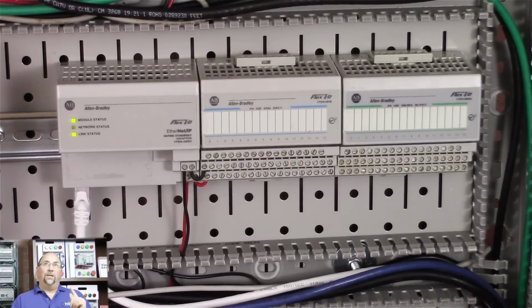And if you see in the overhead cam, this Flex I/O adapter, this Ethernet adapter, is the original one, which you have to set through BootP, because it doesn't have the pinwheels on the front where you can actually set the last octet. Now, we have another video that we've already done in the past, I think it was on the Automation Minute, where we showed you how to set addresses via BootP, so we're not going to do that again.